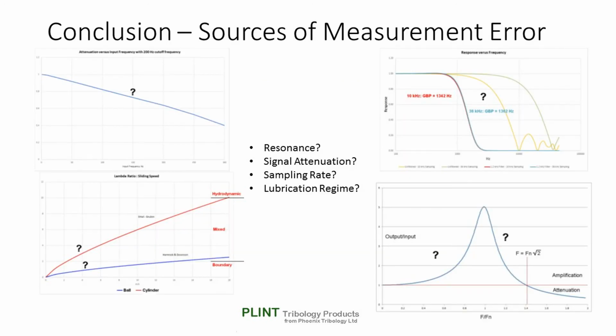To conclude, to understand the indicated value from a reciprocating tribometer friction measurement, we need to know the operating point in terms of both friction force measuring system resonance and the overall measuring system signal bandwidth. The latter, of course, includes any filtering. We also need to use an appropriate sampling rate to avoid aliasing. Ideally, the maximum friction signal frequency of interest should be no more than a third of the natural frequency of the force measuring system, and the reciprocating frequency must be orders of magnitude less than the unfiltered signal bandwidth.